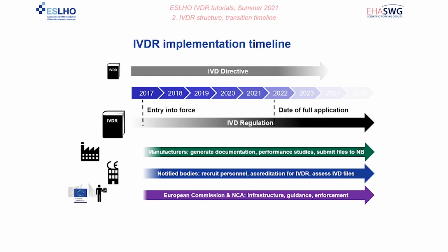They had to perform an analysis of what to do on top of what they already were doing, to show that their devices work as intended, and what else to do in order to fulfill all the requirements of the legislation. At this moment, they are busy filling this gap and generating all the required documentation. If necessary, they are setting up performance studies to collect more clinical evidence. A number of manufacturers have already started with submitting files to their notified bodies for review. Others are still trying to engage with the notified body.